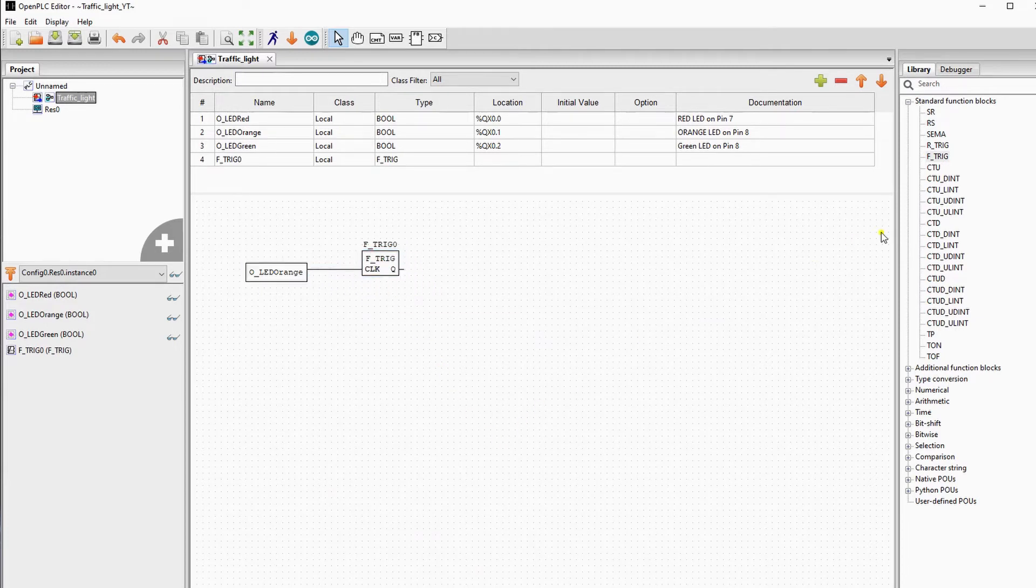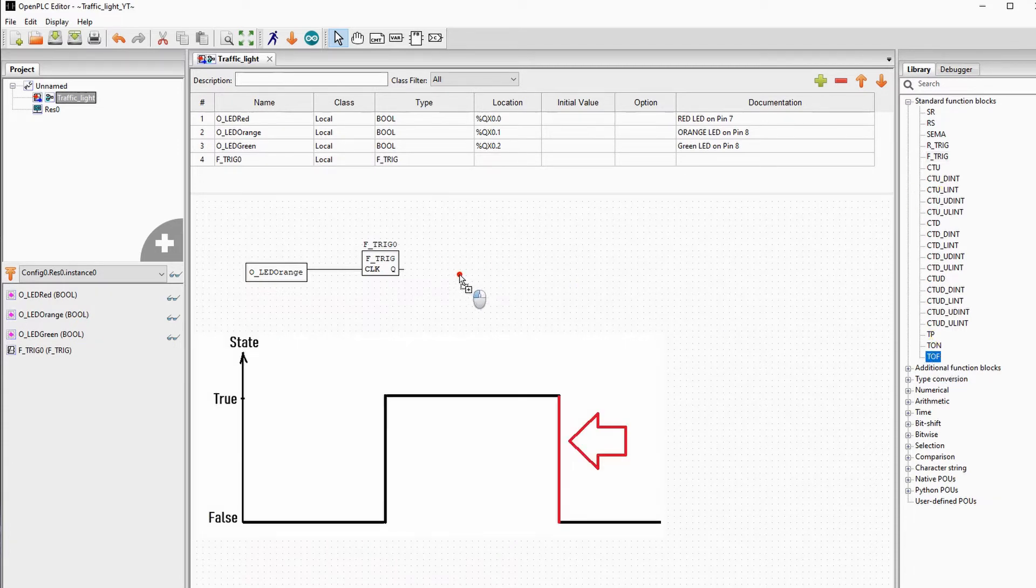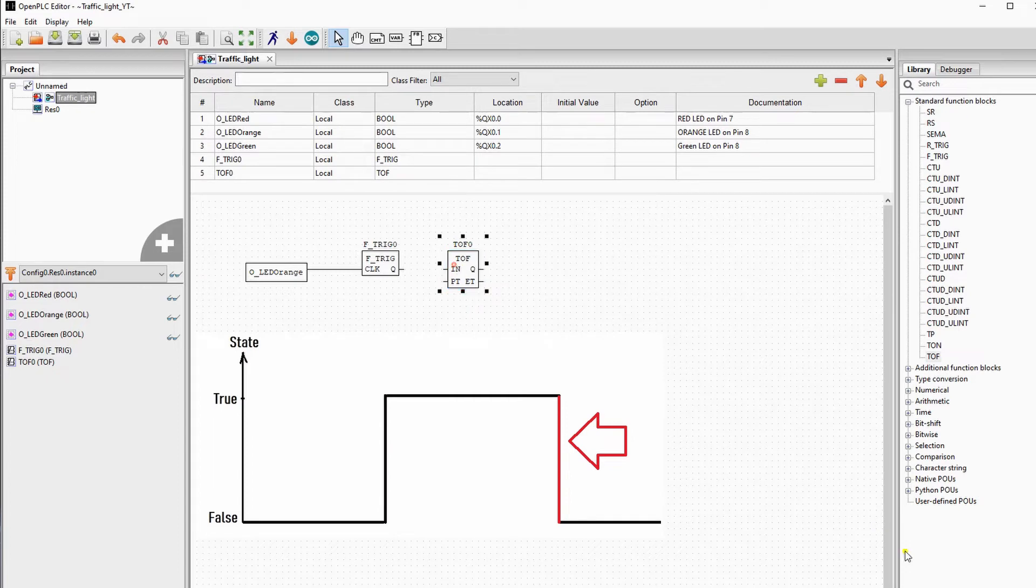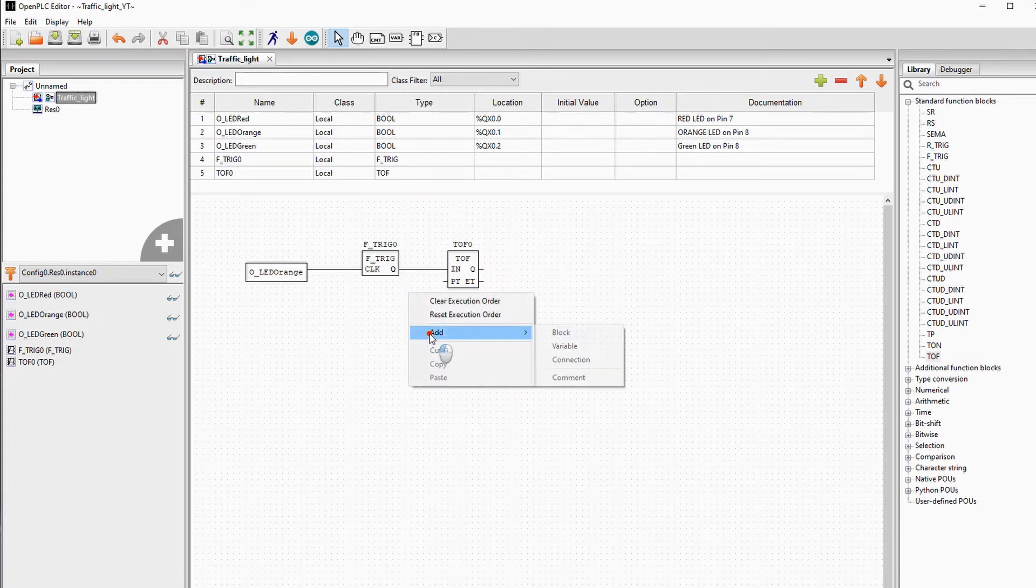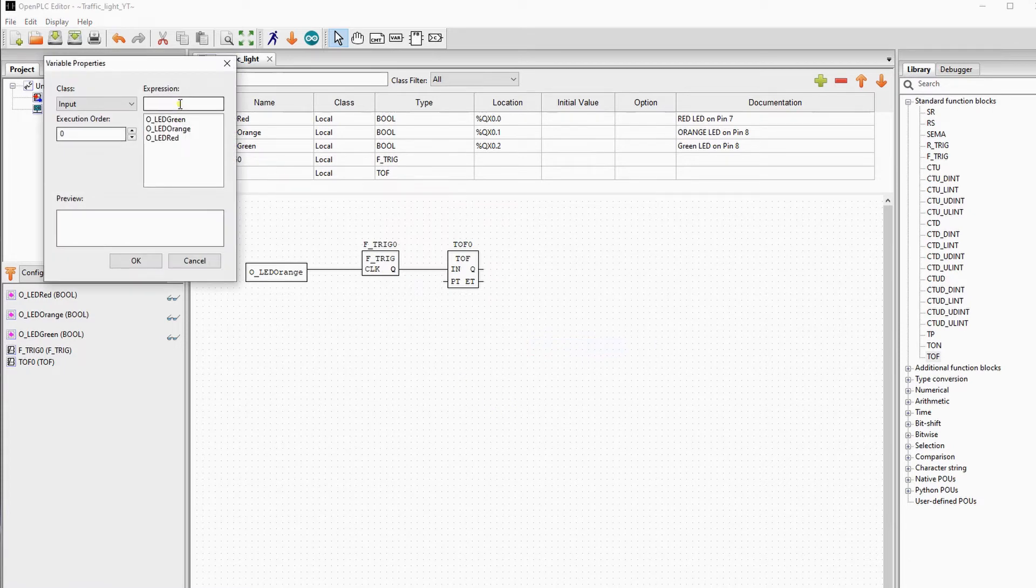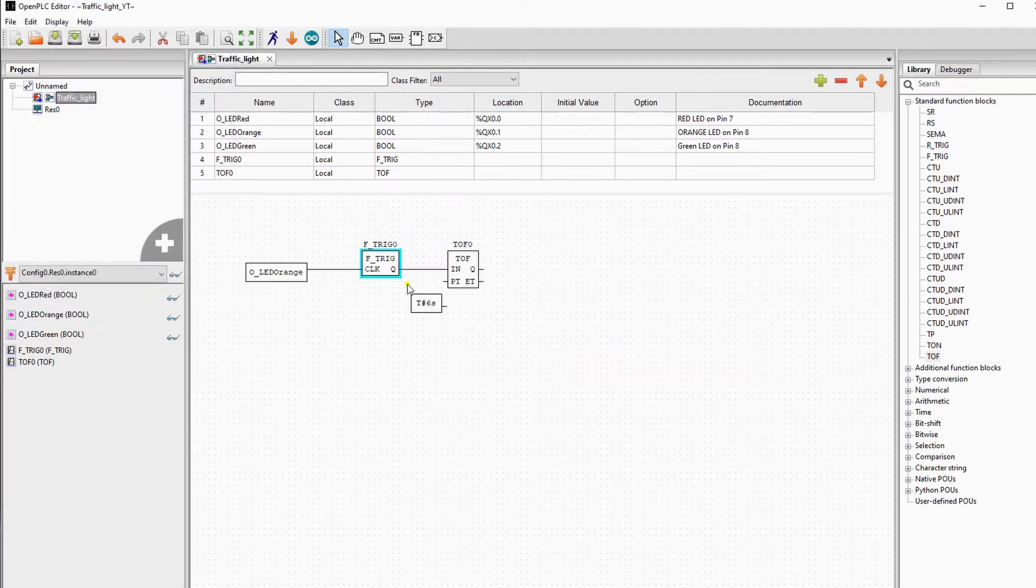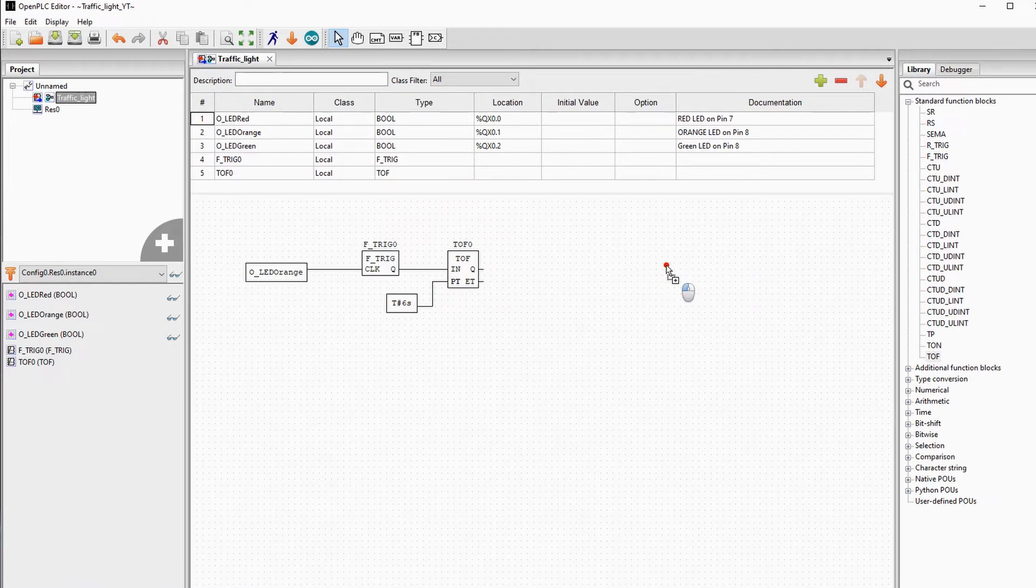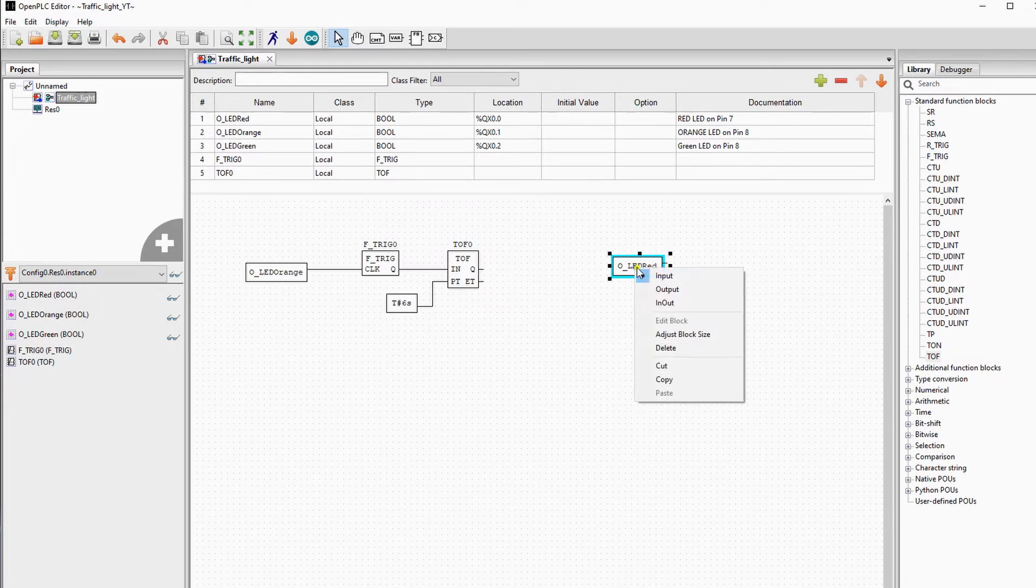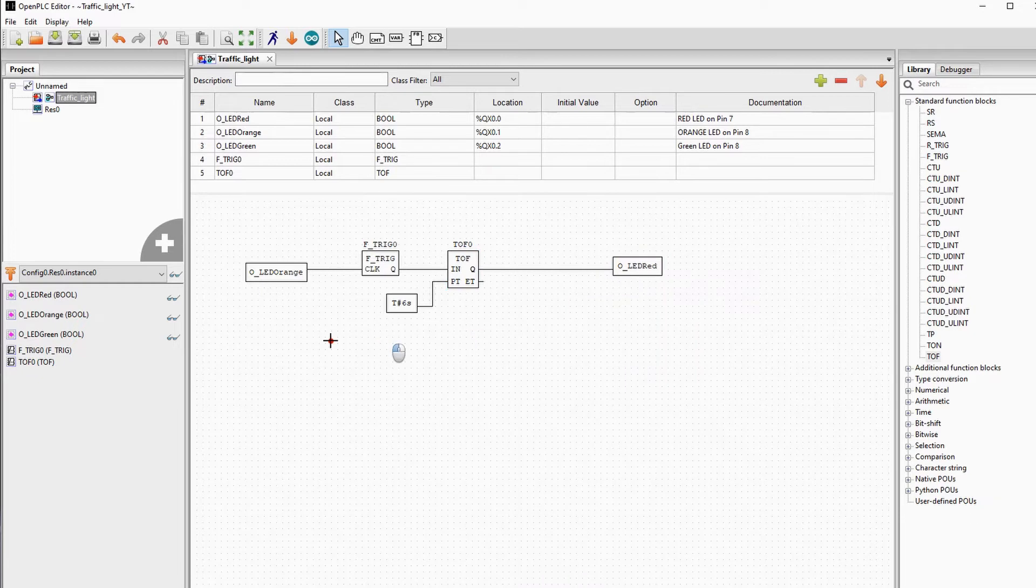The transition from high to low is a negative edge, if you see it in the diagram. We will use this negative edge to start a timer off delay. You have this signal from the F trigger block. It's a 1 when there is a falling edge. We will delay the signal for 6 seconds. So the output of the timer off block will stay high for 6 seconds.